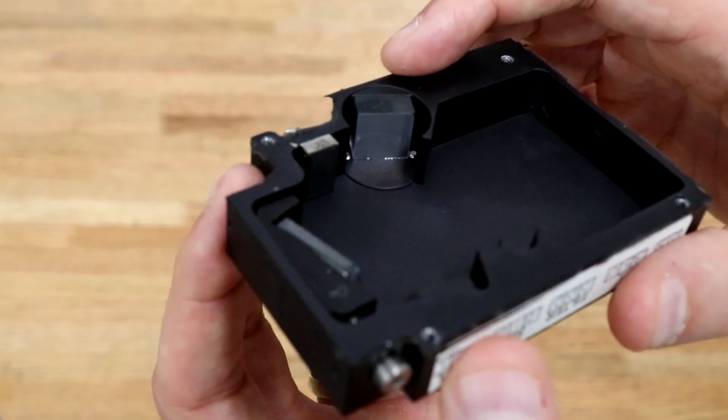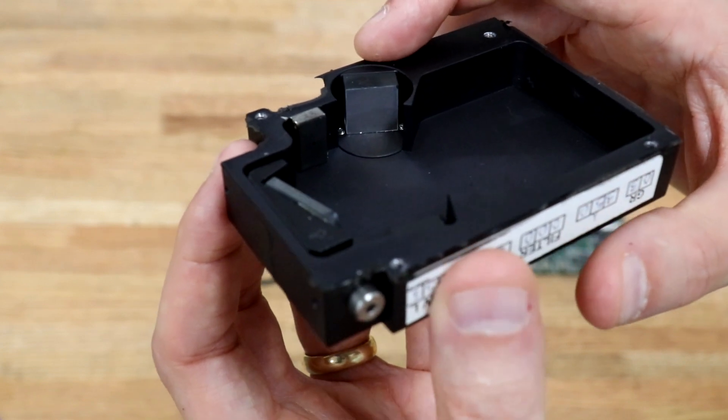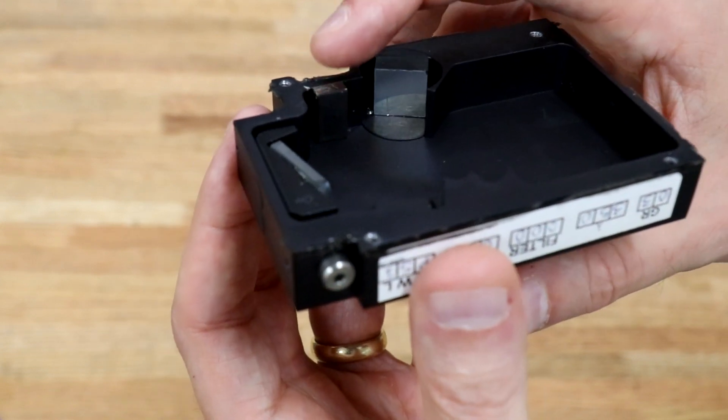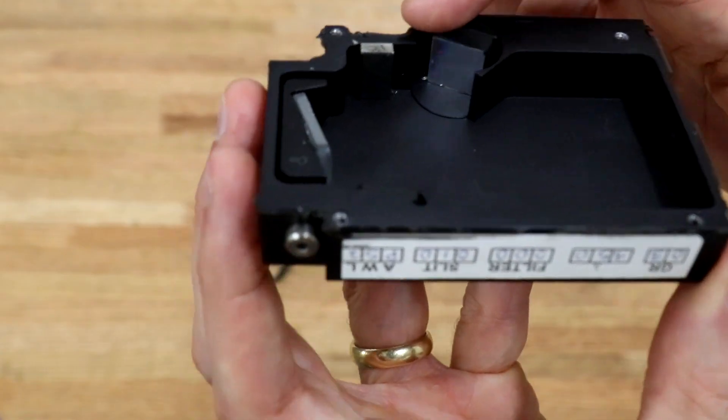The diffraction grating consists of many very small parallel grooves, and reflecting light off of the diffraction grating creates monochromatic versions of the image from the slit. Those images are directed toward a focusing mirror, which directs the light to a detector, which sits over here.